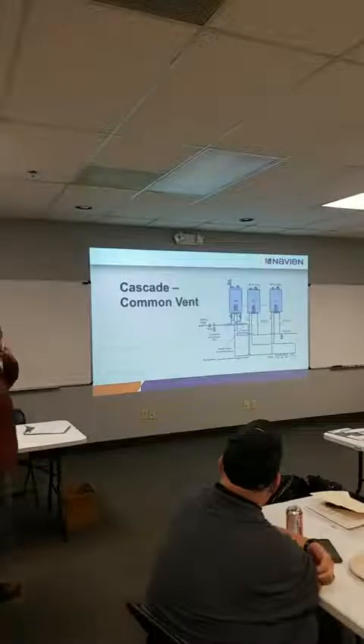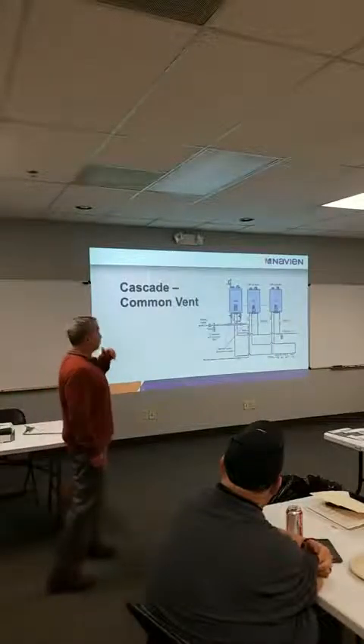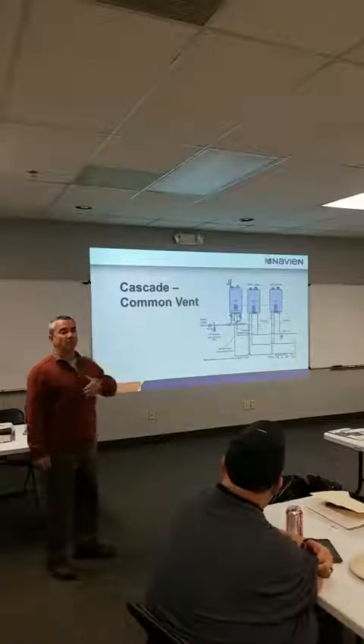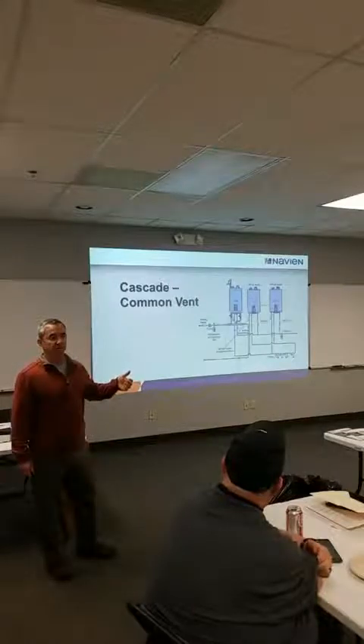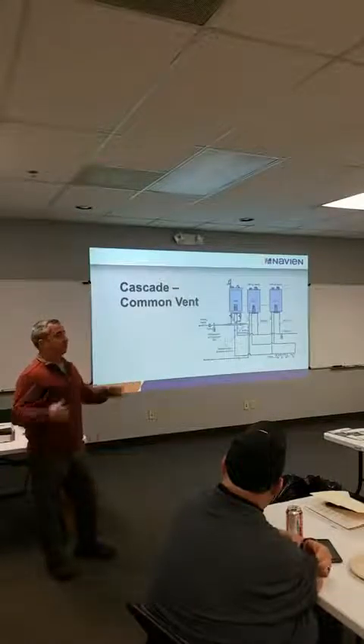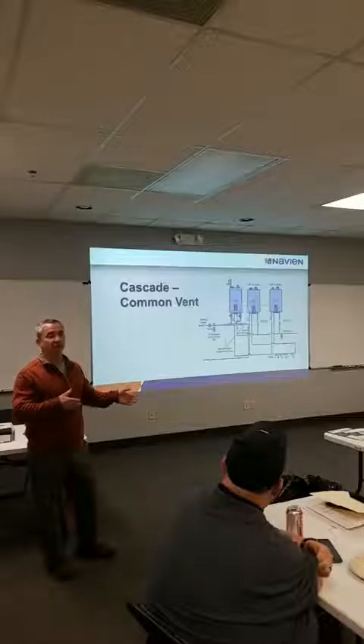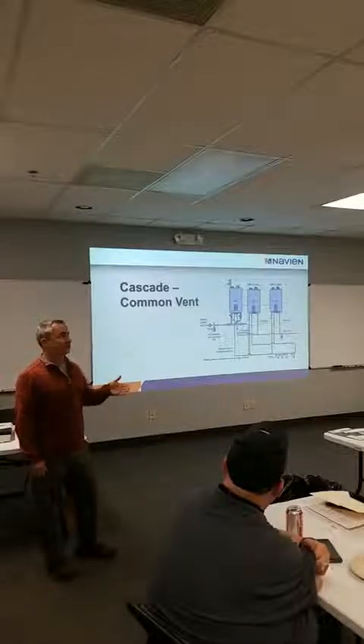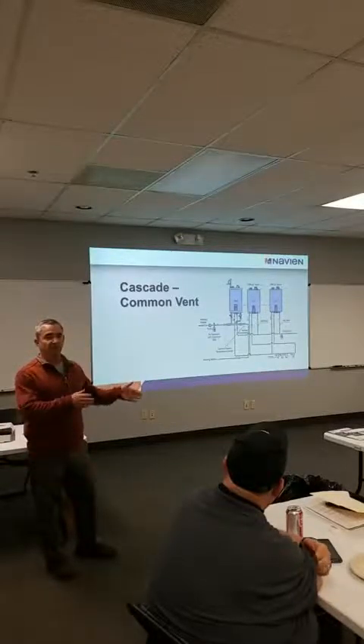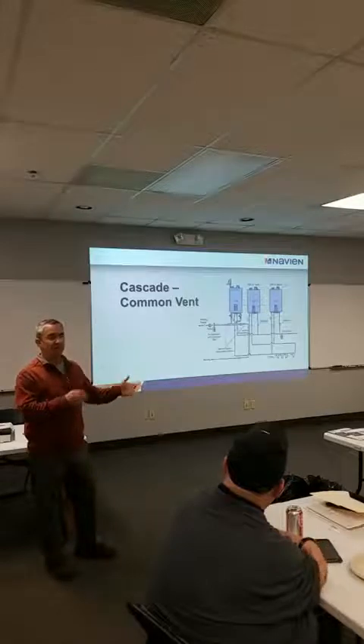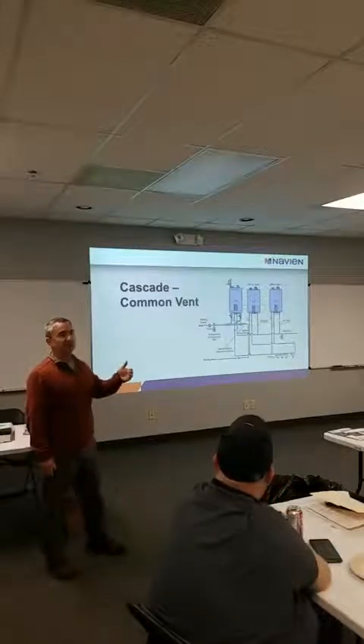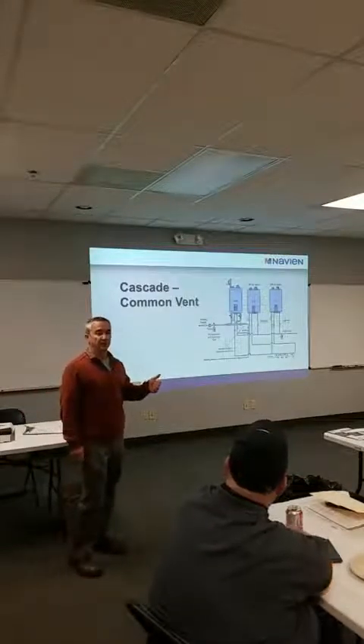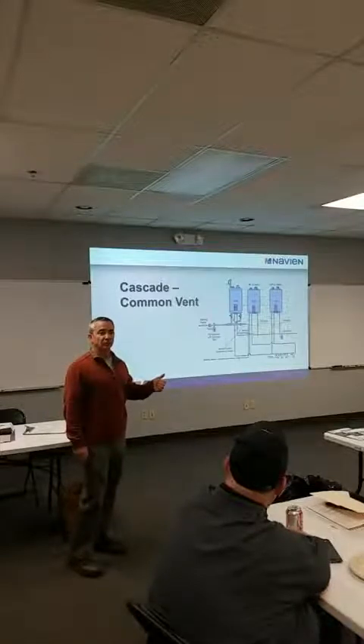Now, with these combis, we can also cascade and common vent multiple water heaters into the system. A lot of times we'll do these big homes where maybe they're just doing radiant floor in the basement. So the combi's great for that job. It's going to give you enough radiant floor heat, but they might have 5-6 bathrooms in the house, and the combi's just not big enough on the domestic side to take care of all those bathrooms.